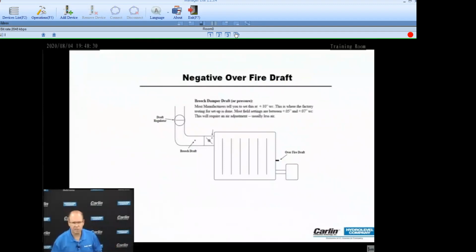We use this slide mostly for commercial training, but in a commercial application, you'll notice there's a damper in the back, and the purpose of the damper is to restrict the flue gases as they leave the boiler. In commercial jobs, I can't tell you how many times technicians feel that opening that damper full wide open makes the burner run better and easier to adjust. And that's not necessarily the case.